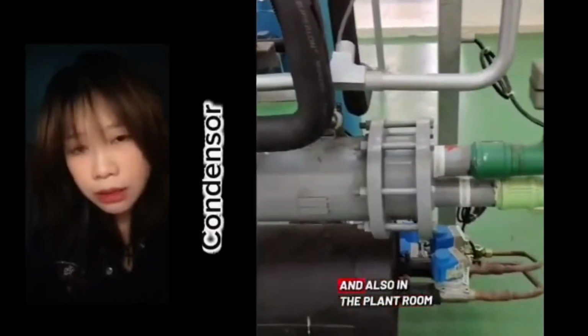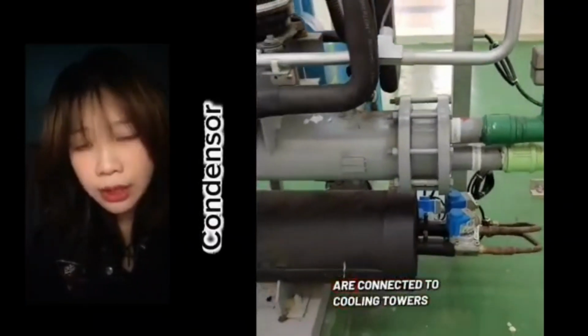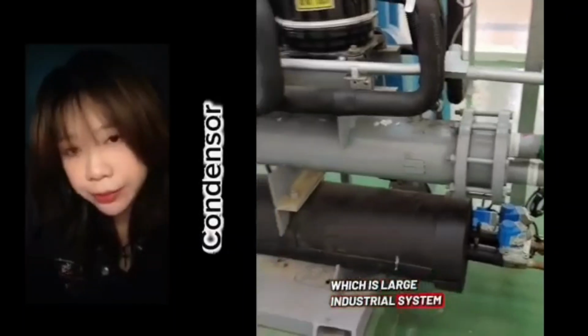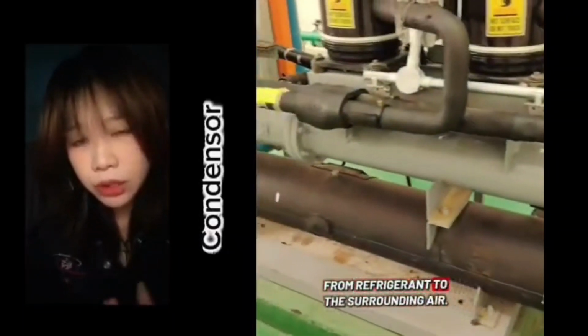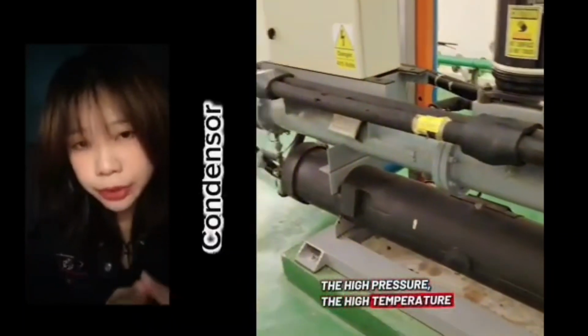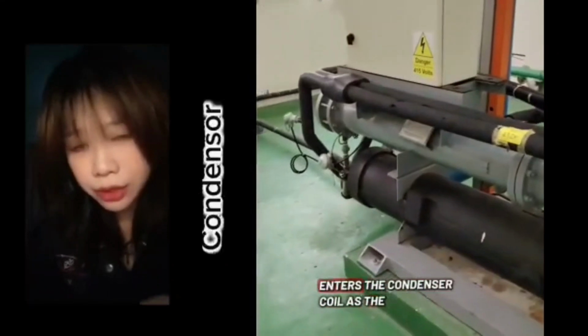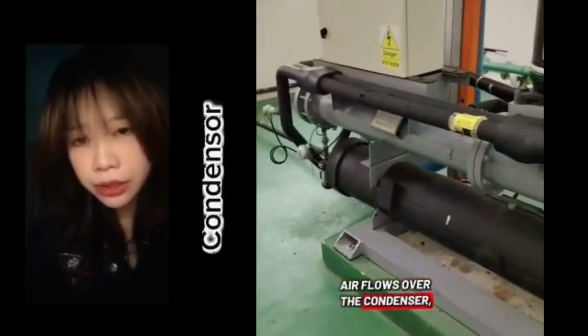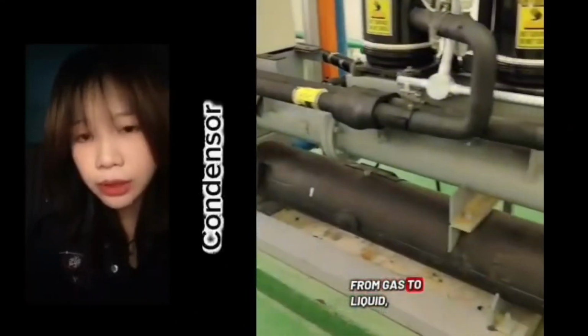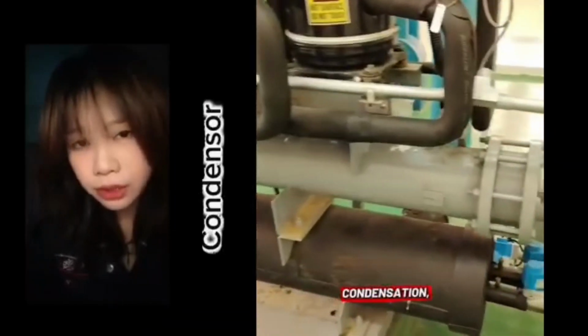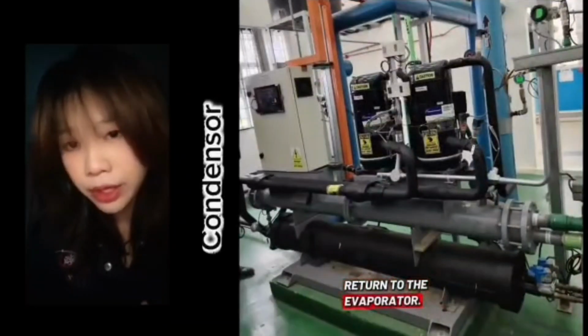The condenser is usually outside the building for the air-cooled type, and also in a plant room for the water-cooled type, or connected to cooling towers, which are a large industrial system. Its function is to release heat from the refrigerant to the surrounding air. The high-pressure, high-temperature refrigerant gas from the compressor enters the condenser coil. As the air flows over the condenser, the refrigerant loses heat and changes from gas to liquid. This process is called condensation, and it prepares the refrigerant to return to the evaporator.